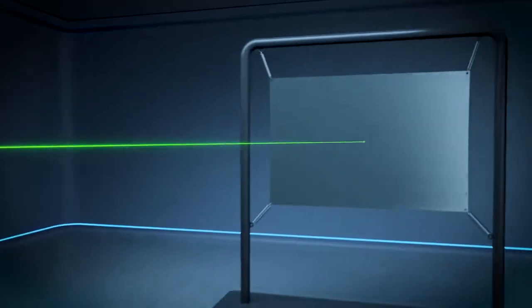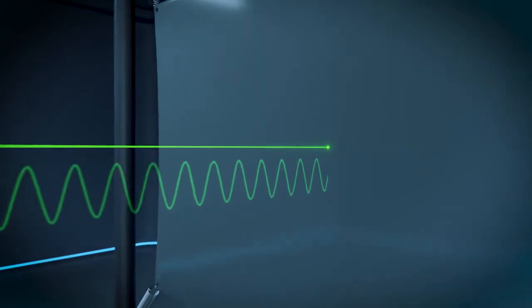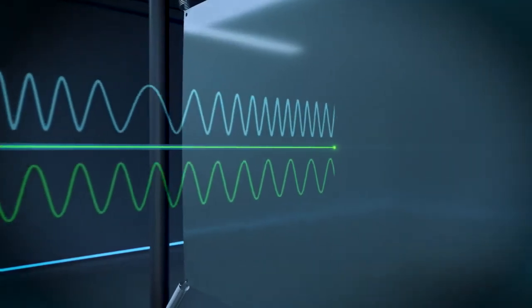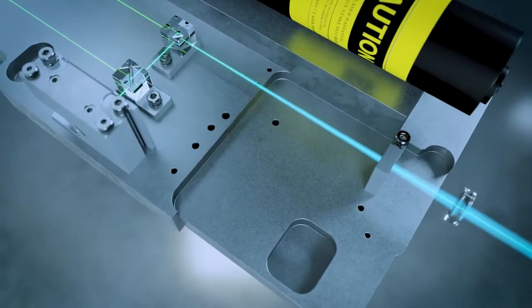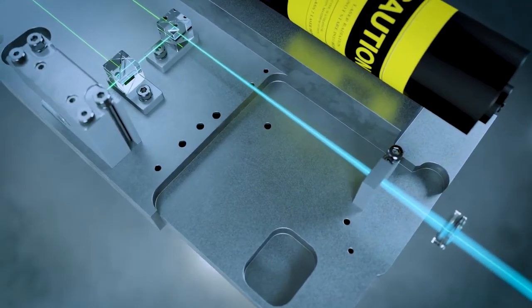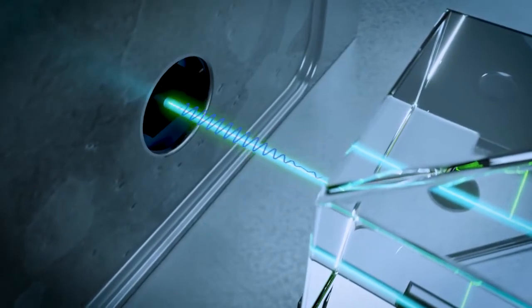Depending on the velocity and displacement, the back scattered light is changed in frequency and phase. The characteristics of the motion are completely contained in the back scattered light. The superposition of this light with the reference beam creates a modulated detector output signal.